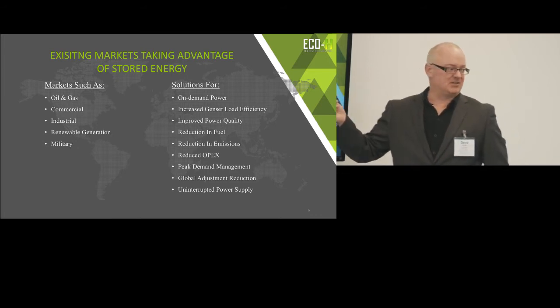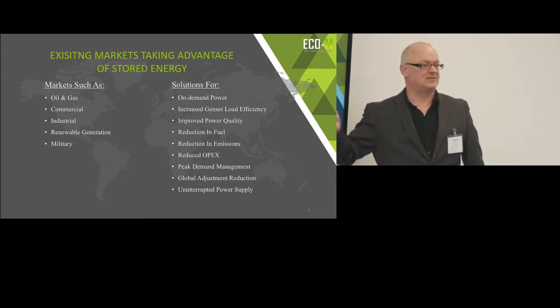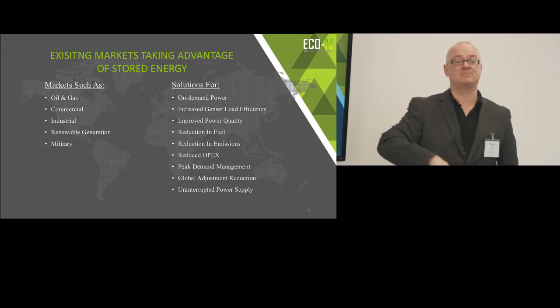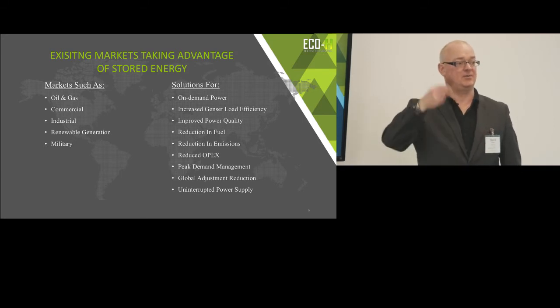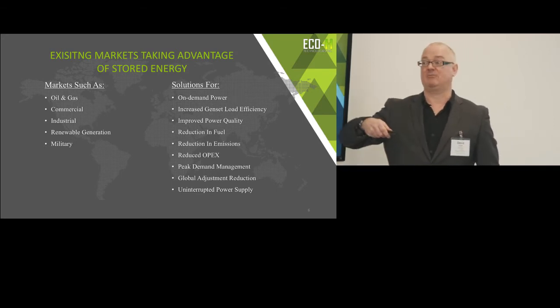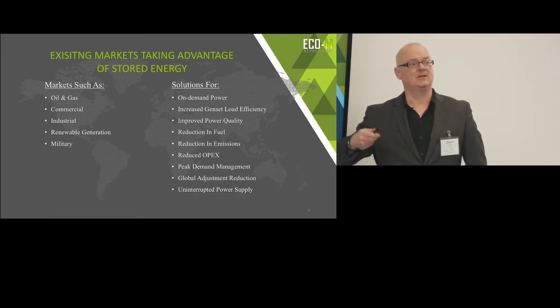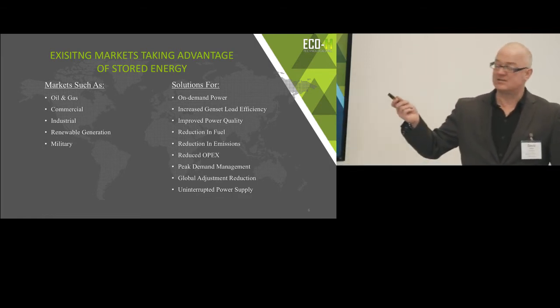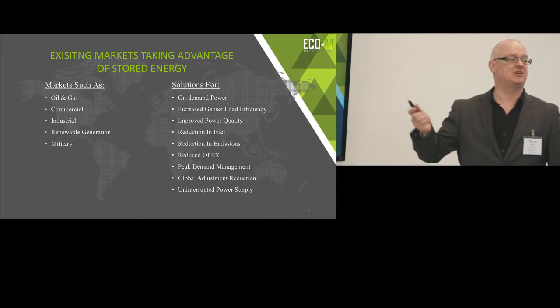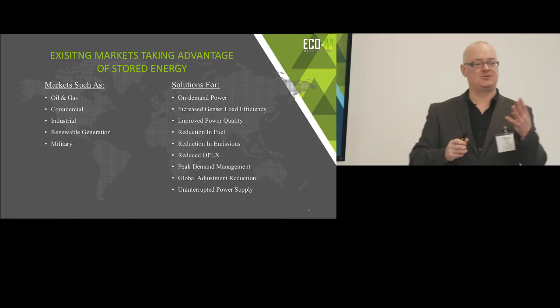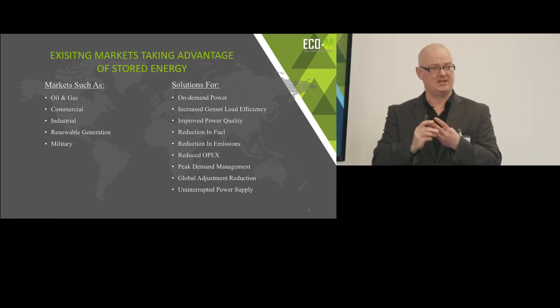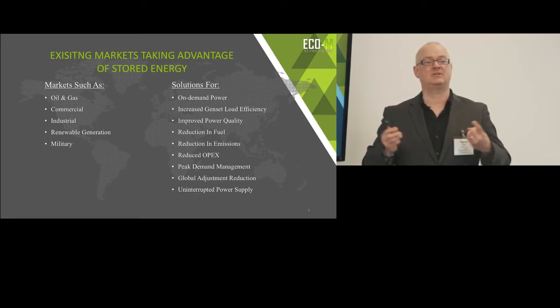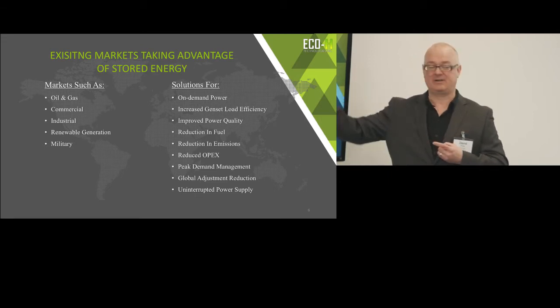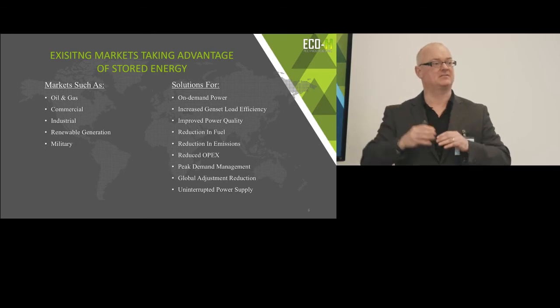With our energy storage system, we could go to the oil and gas industry and take up all these megawatt-plus transients, both positive and negative, charging and discharging at the same time. We noticed we could switch off not 1 generator, but 2. So instead of 4 generators, one a backup and 3 running, 2 of these were switched off, leaving 1 generator running itself for up to 20 to 30 days with a battery storage system taking up all the transients.